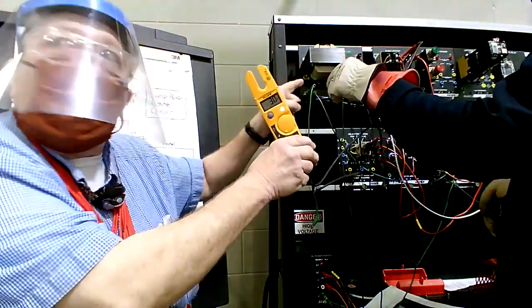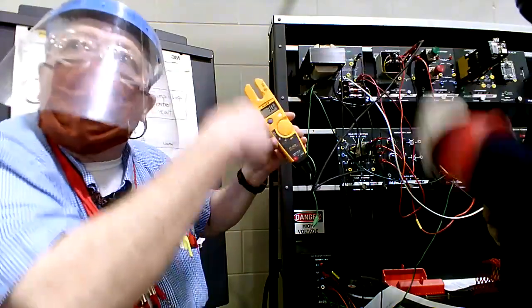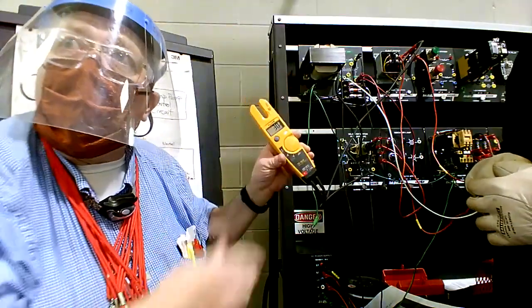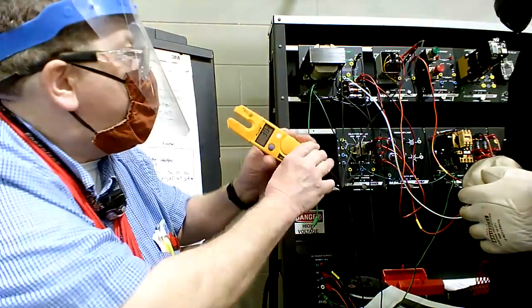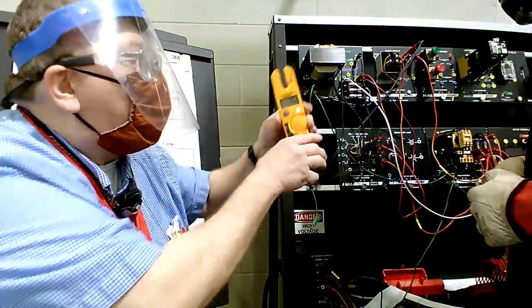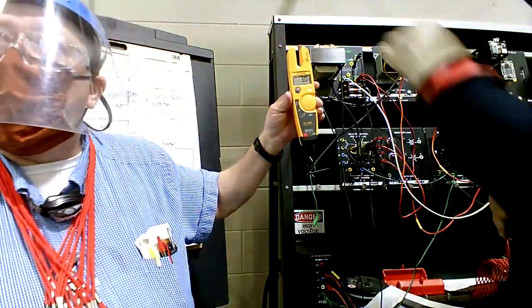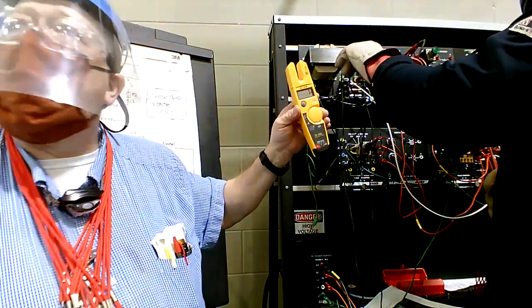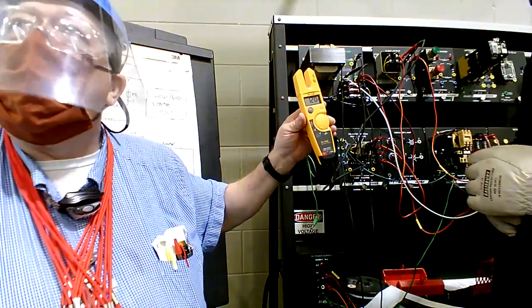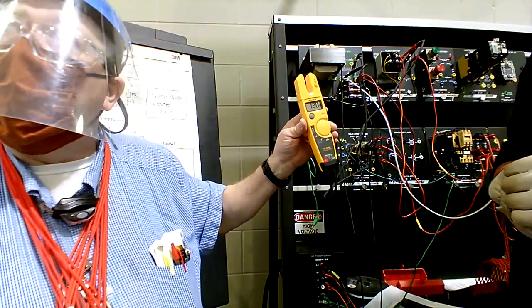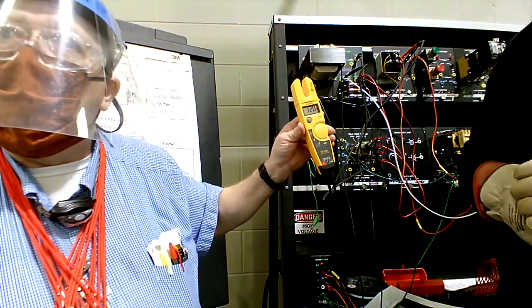You've got to use neutral as a reference point with a meter. Go from neutral to your signal to get the true reading. You get it? But if you go ground to the float, you're going to get a bad reading. So you can't use ground with a meter if you have a floating secondary. That's the bottom line. You can't use ground with a meter.